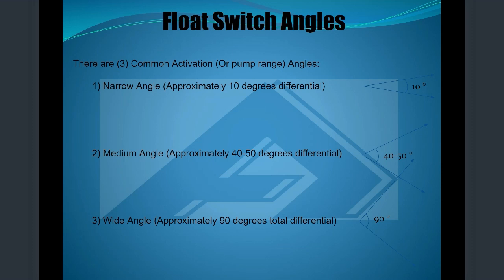So here's activation angle. So narrow angle is approximately 10 degrees above and below horizontal. So deactivate and activate. So there's a pretty narrow range you get. Medium angle is between 40 and 50 degree activation. So you got about 40 degrees up and down. And then the wide angle is 90 degrees. So you're off and you're on, or if it's pumped up, it'd be reversed.